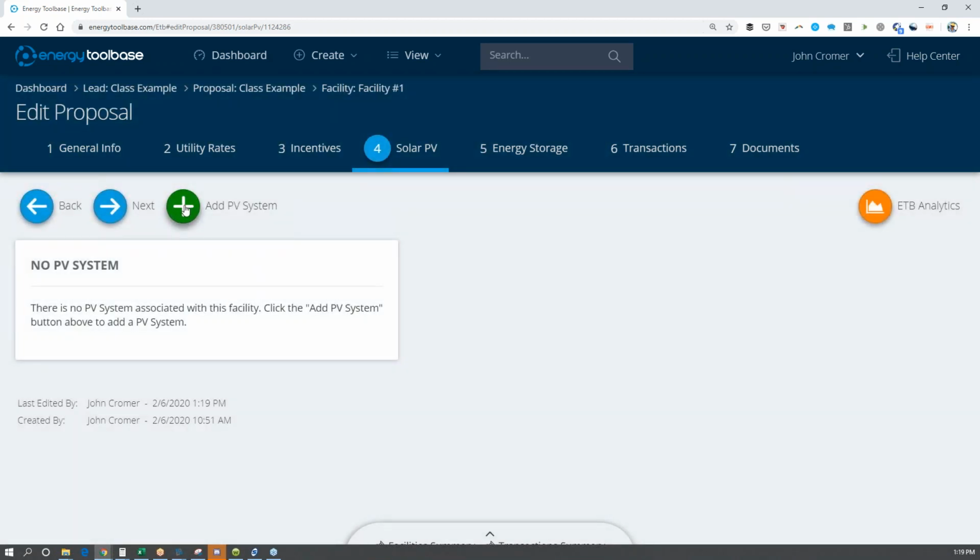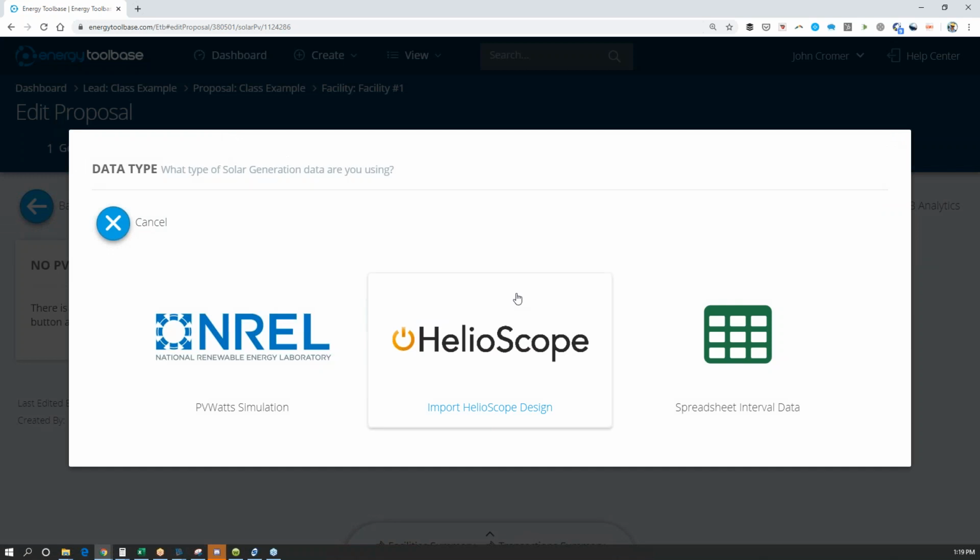Next, we get to our solar array, and this is assuming we already know our array size. Solar on commercial buildings can actually be easier to size than on residential, because often on flat open commercial roofs you don't have to worry about trees, and so you can make assumptions about heights of things and overassume. And that air conditioning unit is 5 feet tall, so we can use trigonometry to determine shadow lengths of 5 foot tall objects or 3 foot tall parapet walls.